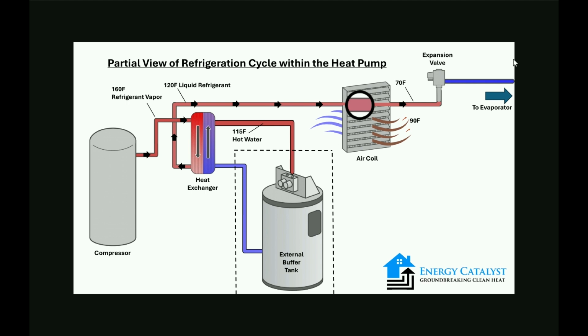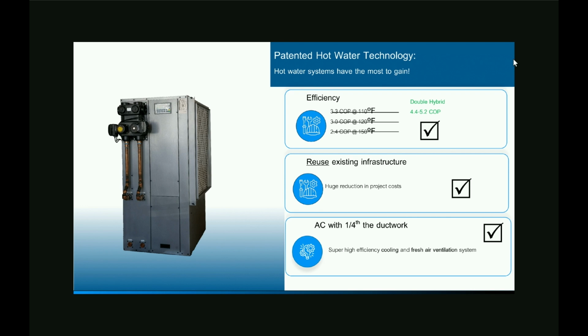So we can take 70-degree air, pass it through an air coil, and use that as a subcooler. Now we're delivering 70-degree refrigerant into that expansion valve instead of 120-degree. We're also releasing heat directly into the building. We're making hot air and hot water at the same time. This is what we call the double hybrid refrigeration cycle.